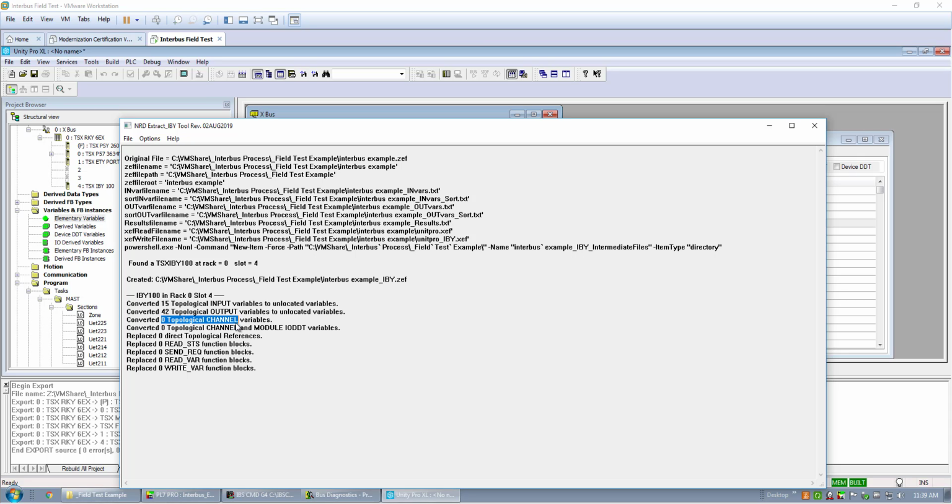to a DFB. So the variables stay the same as they are in the application. Whatever they named it for module or channel, that'll get translated over into M580. So they'll get the same data. It is just being handled a little bit differently. It's either using a DFB. If they happen to be using send request or read var or write var functions, what's going to happen is it's going to replace that with a DFB using data exchange. So it performs all the same functions, it just manages it a little bit differently, but the solve is identical.